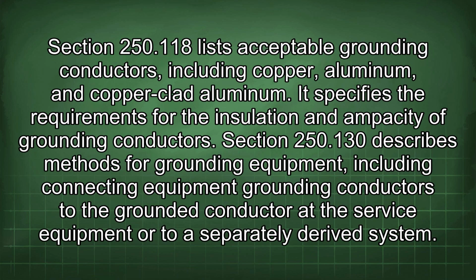Section 250.118 lists acceptable grounding conductors, including copper, aluminum, and copper-clad aluminum. It specifies the requirements for the insulation and ampacity of grounding conductors. Section 250.130 describes methods for grounding equipment, including connecting equipment grounding conductors to the grounded conductor of the service equipment or to a separately derived system.